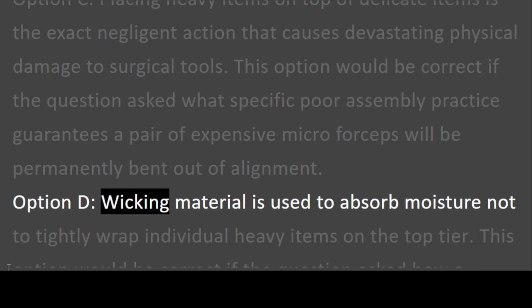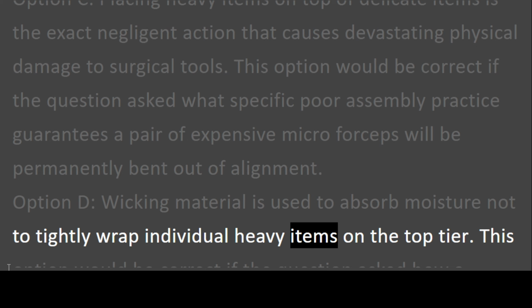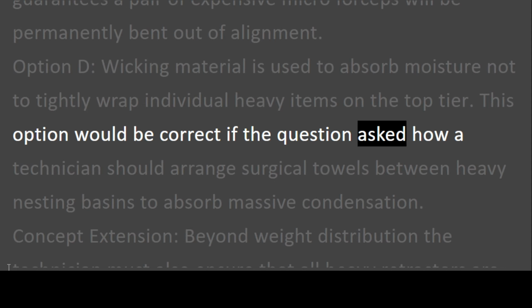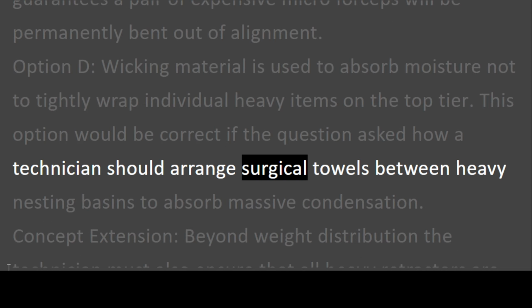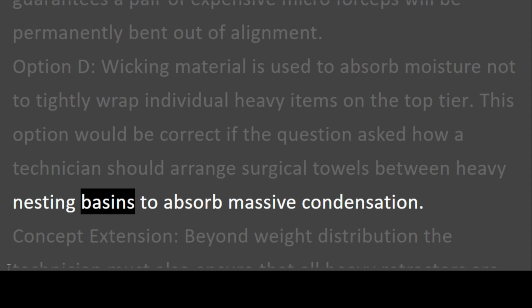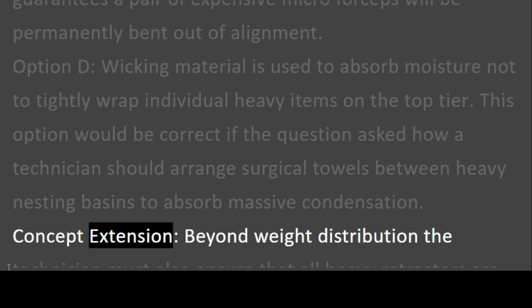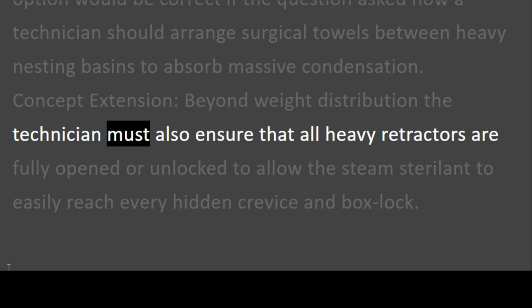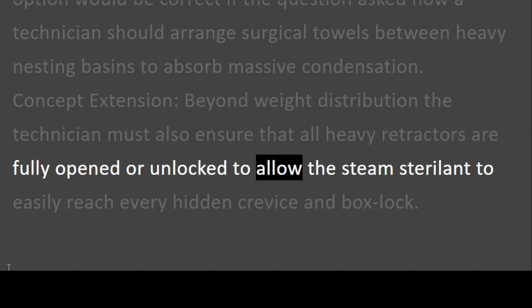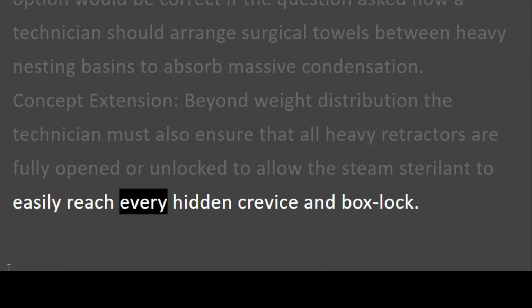Option D. Wicking material is used to absorb moisture, not to tightly wrap individual heavy items on the top tier. This option would be correct if the question asked how a technician should arrange surgical towels between heavy nesting basins to absorb massive condensation. Concept extension. Beyond weight distribution, the technician must also ensure that all heavy retractors are fully opened or unlocked to allow the steam sterilant to easily reach every hidden crevice and box lock.